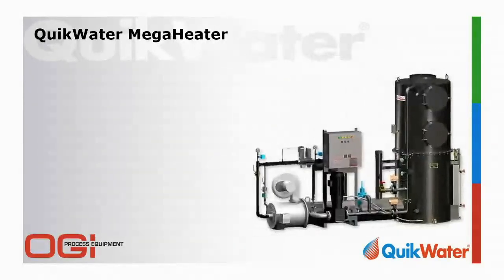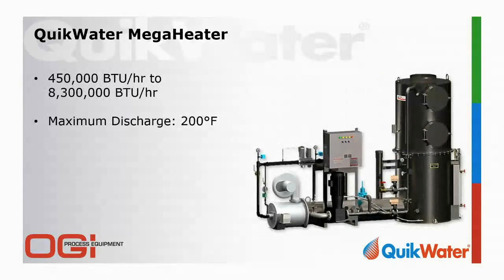Today, we're going to talk about the QuikWater MegaHeater. This MegaHeater is used in applications where the customer requires hot water over 180 degrees. The MegaHeater can effectively and efficiently produce water up to 200 degrees Fahrenheit. The MegaHeater is available in sizes from 450,000 BTUs per hour to 8.3 million BTUs per hour. Like the flagship, there are a wide range of controls and options available.